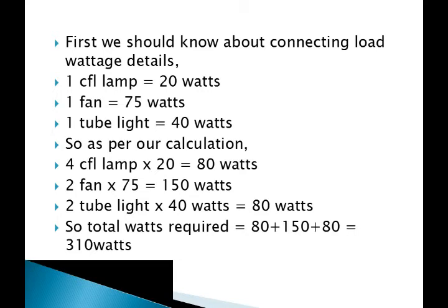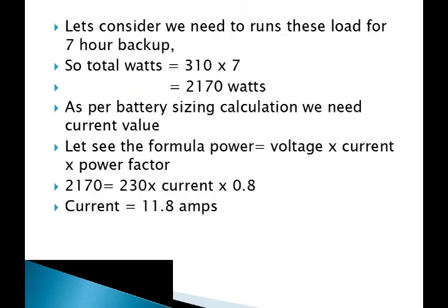So total watts needed: 80 plus 150 plus 80 equals 310 watts. We need to run this load for 7 hours of backup. So total watt-hours equal to 310 multiplied by 7, which equals 2170 watt-hours.